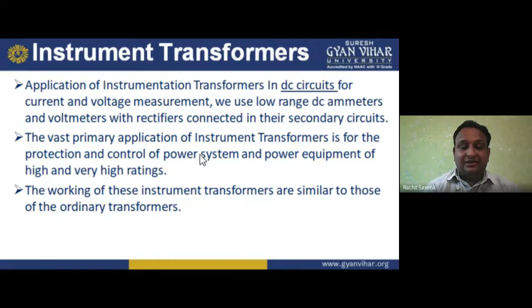The difference from the ordinary transformer is that here we have H1 and H2 as the primary winding, and X1 and X2 as the secondary winding. In a main transformer, the primary winding is represented by P1 and P2, and the secondary winding by S1 and S2. But for the instrument transformer, as per IEEE or IEC specification, the primary terminals are represented as H1 and H2, and the secondary winding is always represented as X1 and X2. I hope you understand.